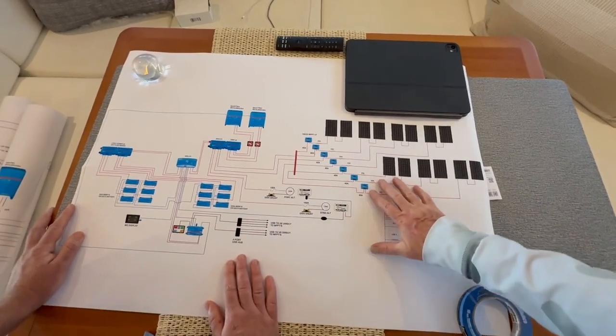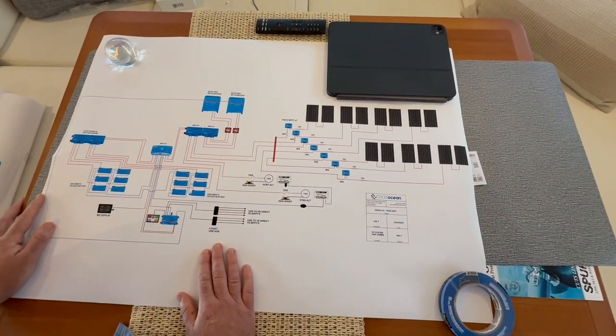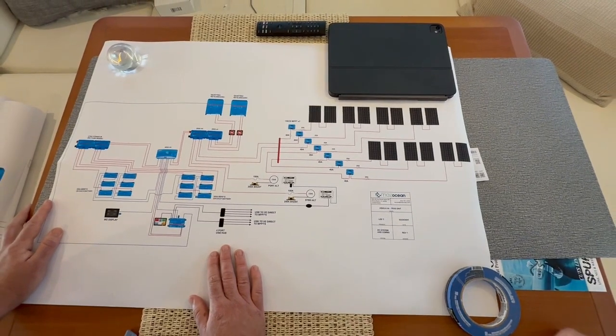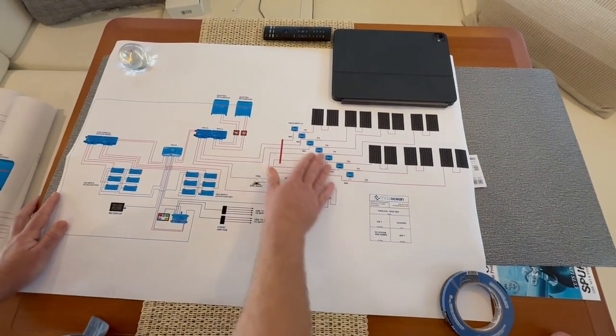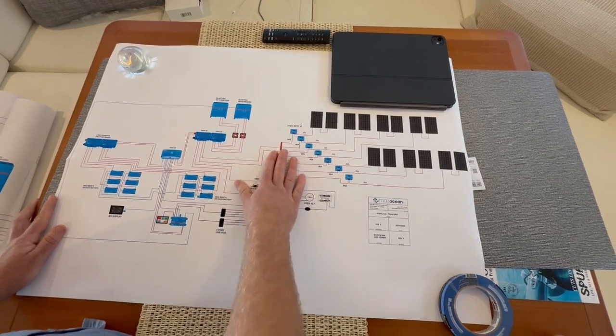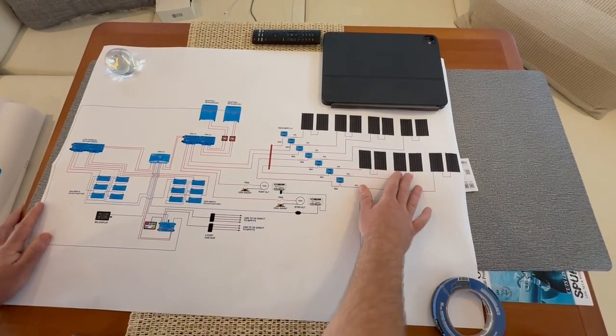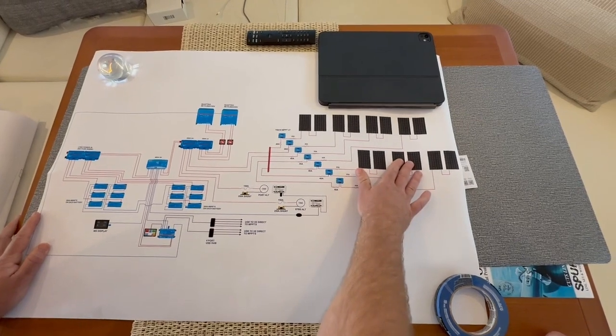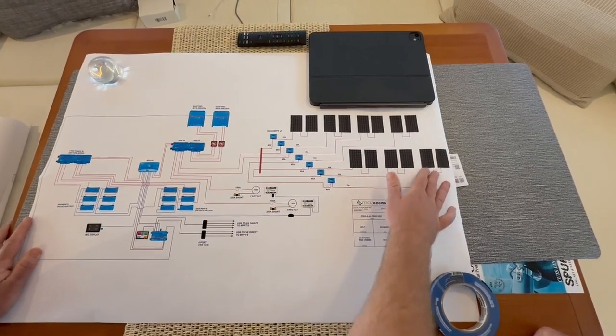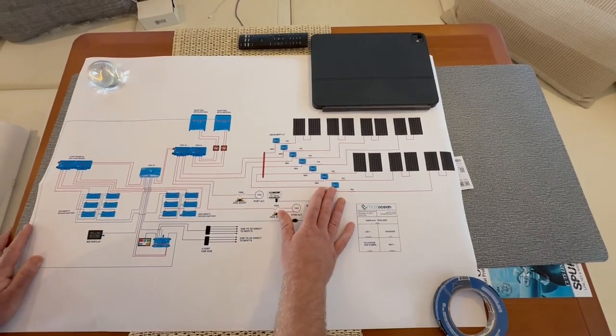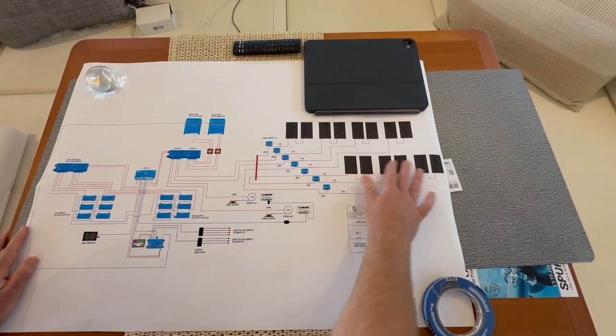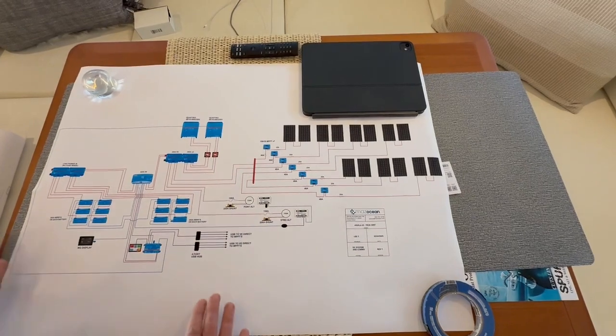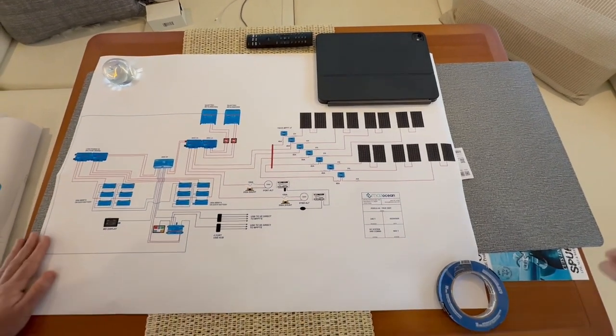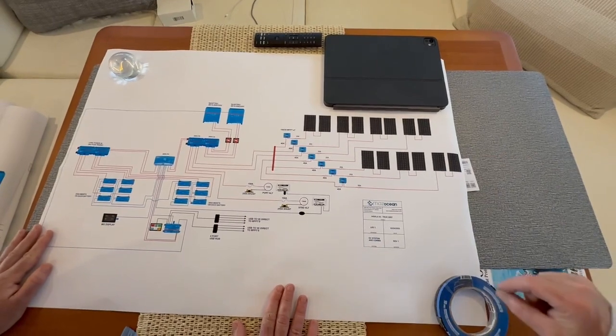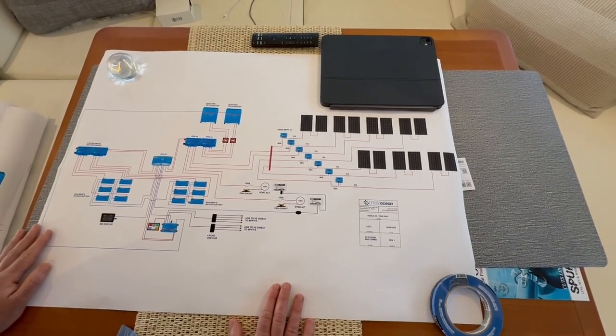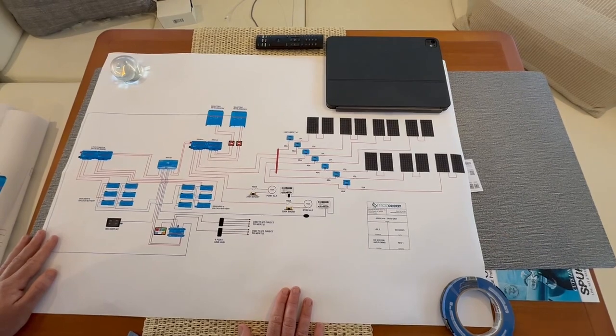Typically you don't see this many MPPT controllers. Why did we do that? Once again, redundancy and shading reasons. The more MPPTs you have, the more likely you are to produce power. We could have wired four in series if we wanted, but if two of them got shaded, it could bring down all four. By having more MPPTs, we ensure that if, say, two panels are shaded, it's not affecting any of the other panels. So we're optimizing efficiency by using more MPPT controllers to ensure maximum production, and if one goes down, you don't lose half your system.